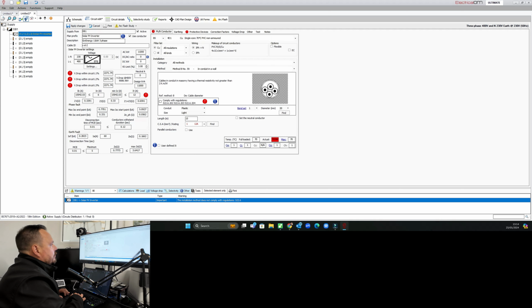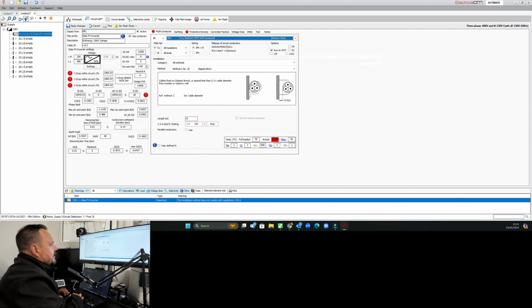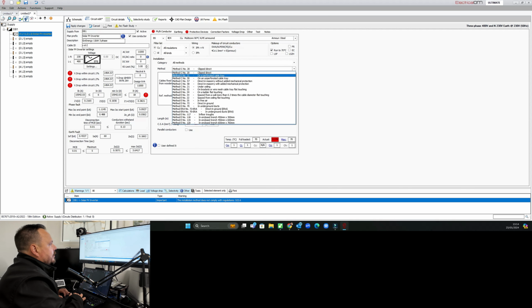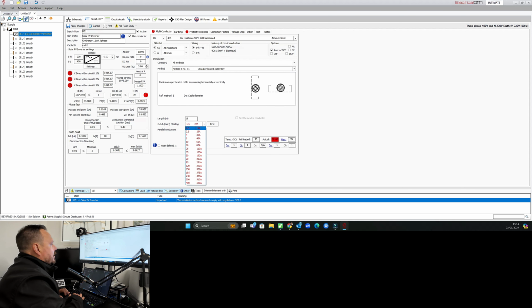So for our phase neutral conductors, we're going to go for an XLPE cable, but we'll run it at 70. Again, we'll say that it's going to be on perforated cable tray. We need to set our length, which is going to be about 15. So that can pop on there, and our cable size will go for 10 mil.